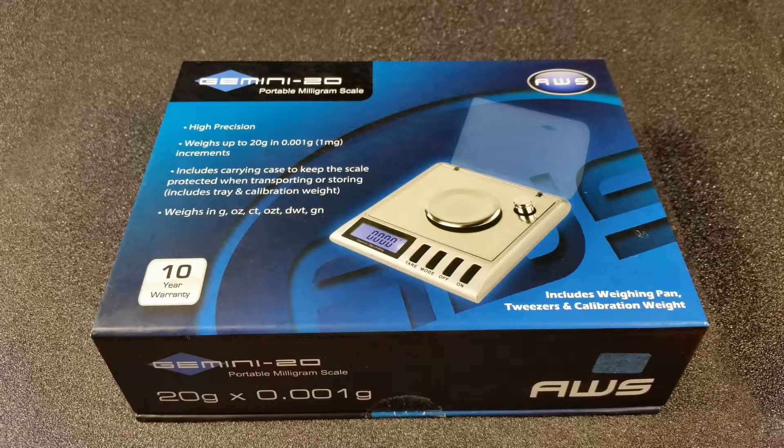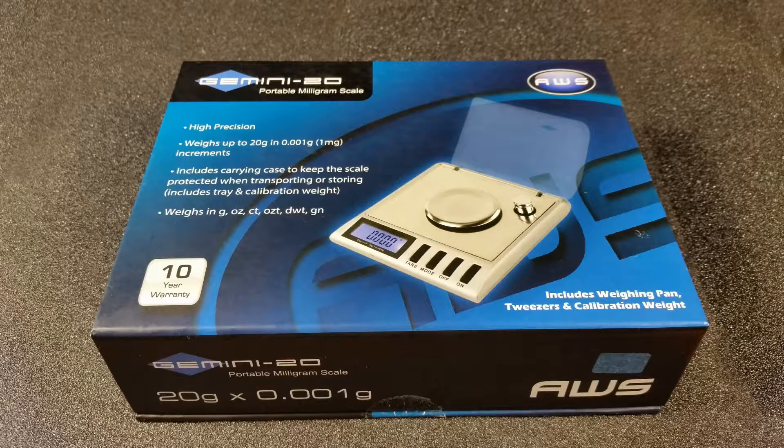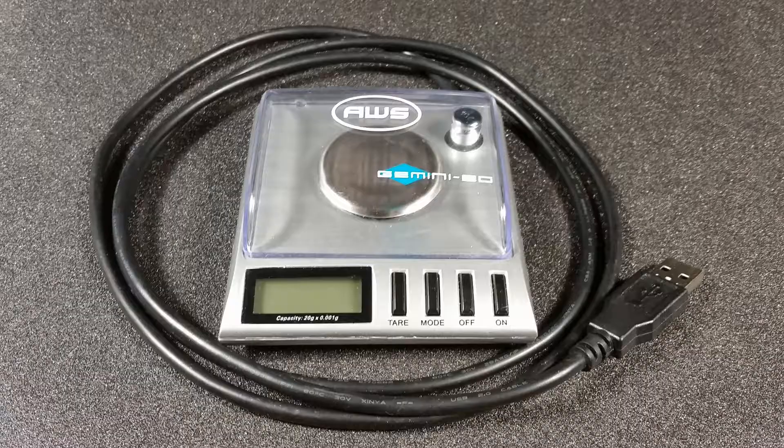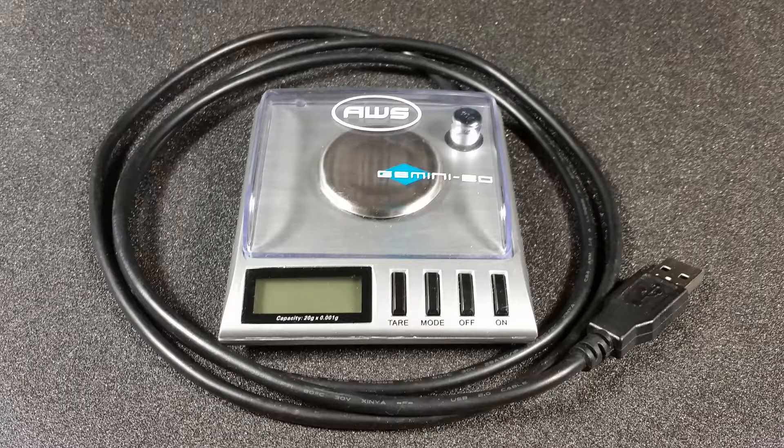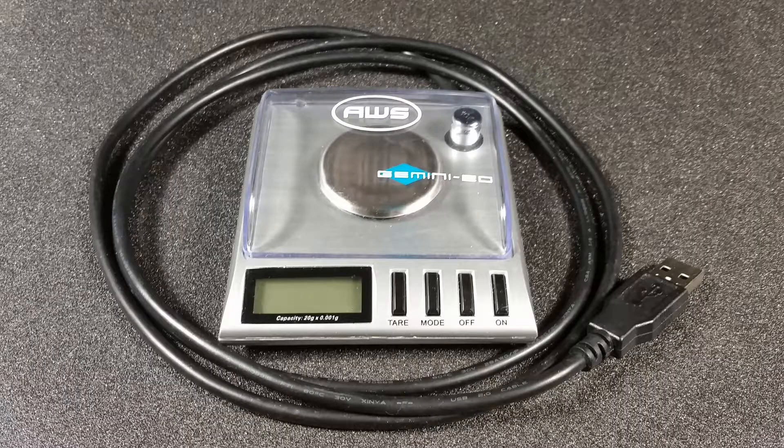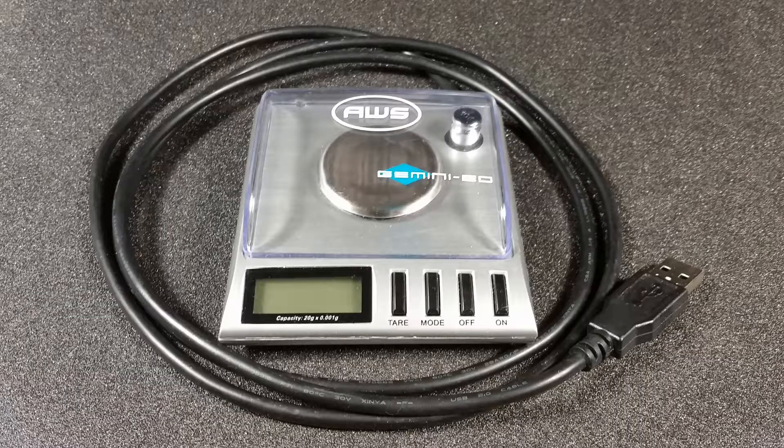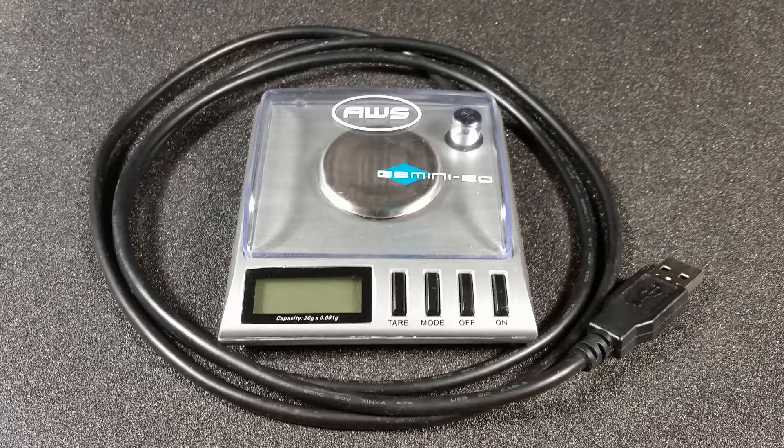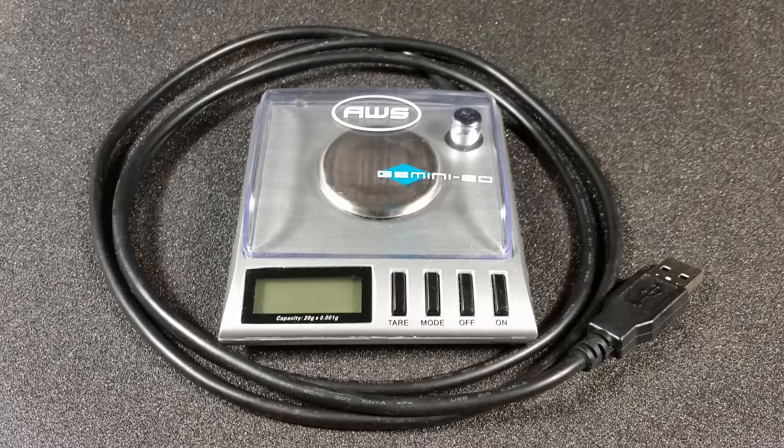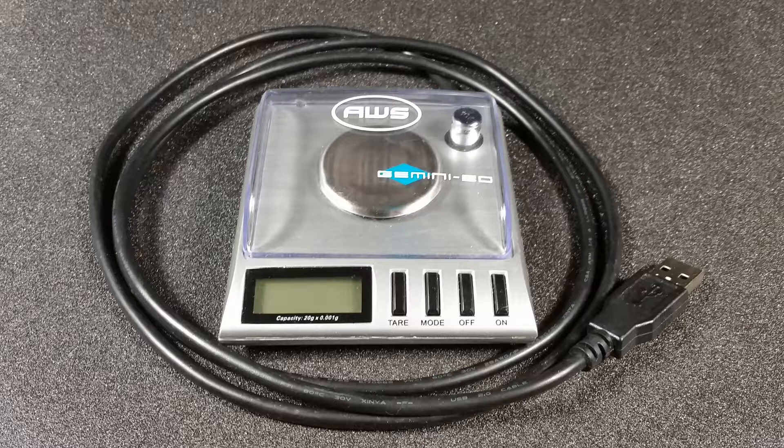This is a typical low-cost scale using chip-on-board technology. It's a Gemini 20 milligram scale which has been modified for measurement capture. The microprocessor has been built into the unit and the USB connection is used for data transmission and to supply power to both the scale and the microprocessor.